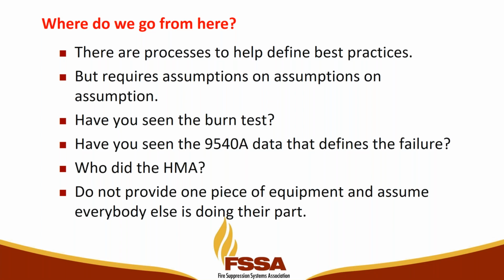Ask for the burn test. Have they done the data? Where's the 9540A data that helps define the hazard? Have they done an HMA? If they're asking you to provide a system, show me where you've done the hazard mitigation analysis proving this is an acceptable way to mitigate your failures. Do not provide one piece of equipment and assume everybody else is doing their part.